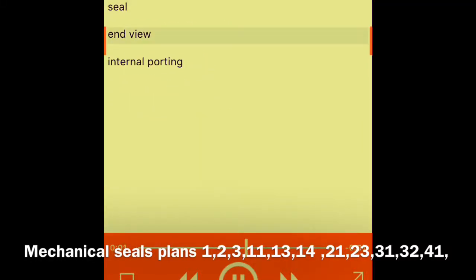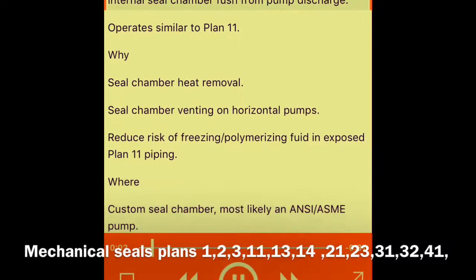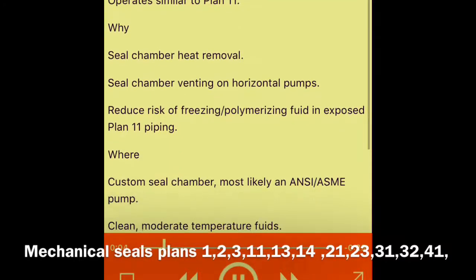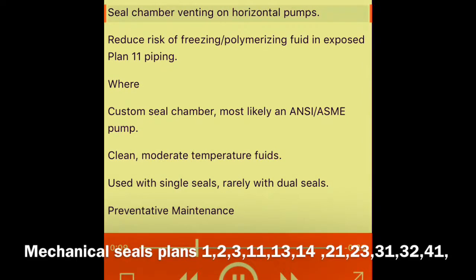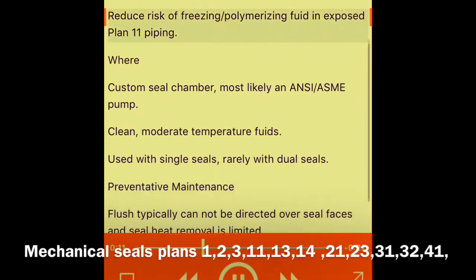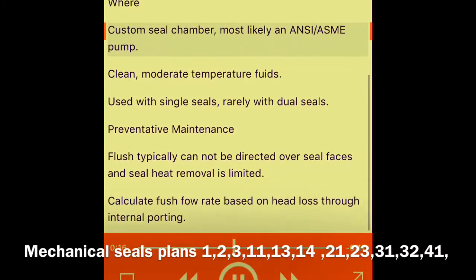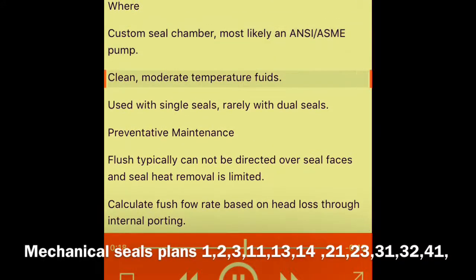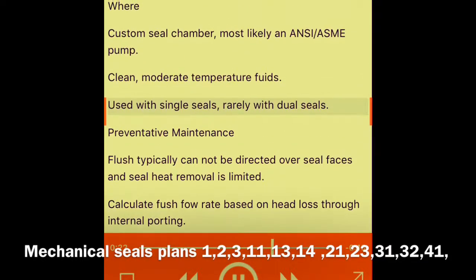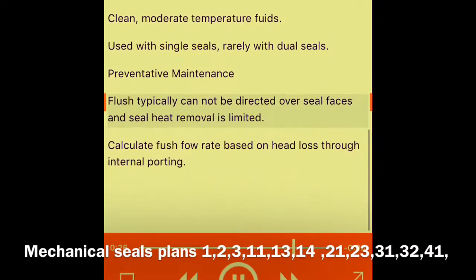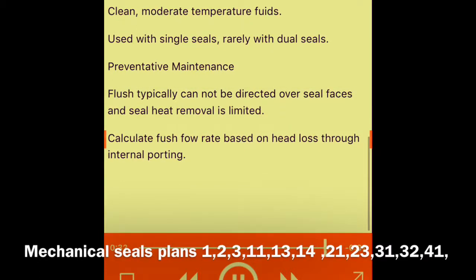Plan 01 — seal end view, internal porting. What: internal seal chamber flush from pump discharge. Operates similar to Plan 11. Why: seal chamber heat removal, seal chamber venting on horizontal pumps, reduce risk of freezing, polymerizing fluid in exposed Plan 11 piping. Where: custom seal chamber, most likely an ANSI/ASME pump; clean, moderate temperature fluids. Used with single seals, rarely with dual seals. Preventative maintenance: flush typically cannot be directed over seal faces and seal heat removal is limited. Calculate flush flow rate based on head loss through internal porting.